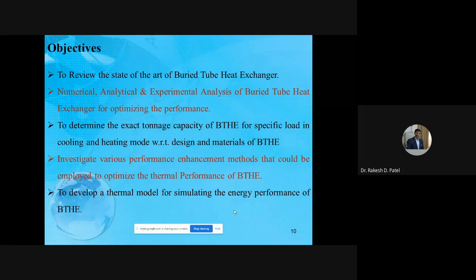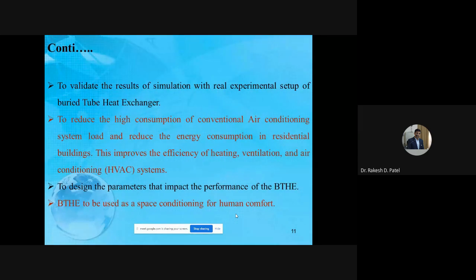Now, what is the objective of this heat exchanger or this research? First, to review the state of the art of the buried tube heat exchanger. Second, the numerical, analytical, and experimental analysis of this BTHE or earth tube heat exchanger for optimizing the performance. Third, to determine the exact tonnage capacity of the heat exchanger for a specific load in cooling as well as heating mode, with respect to design and material of the heat exchanger. Next, to investigate the various performance enhancement methods that could be employed to optimize the thermal performance of the buried tube heat exchanger. And next, to develop a thermal model for simulating the energy performance of a heat exchanger.